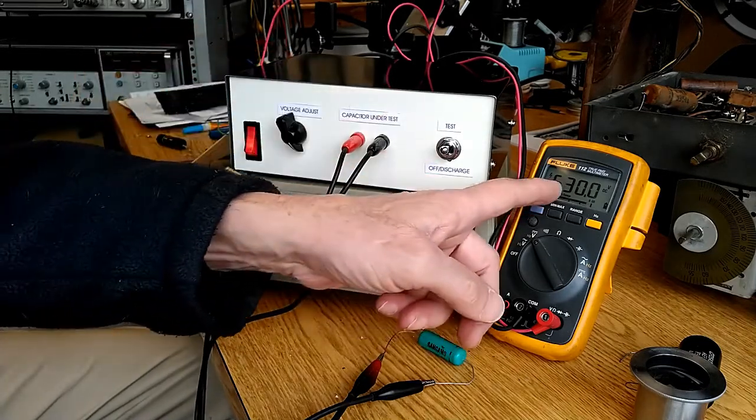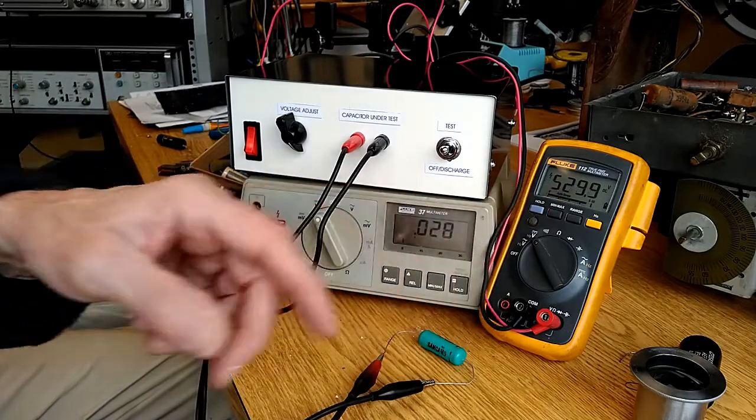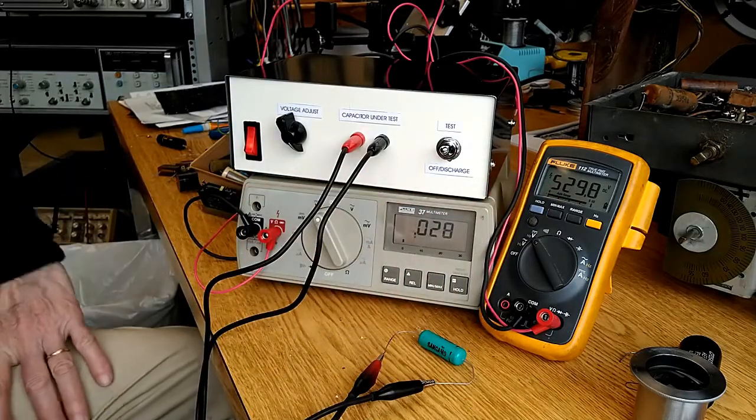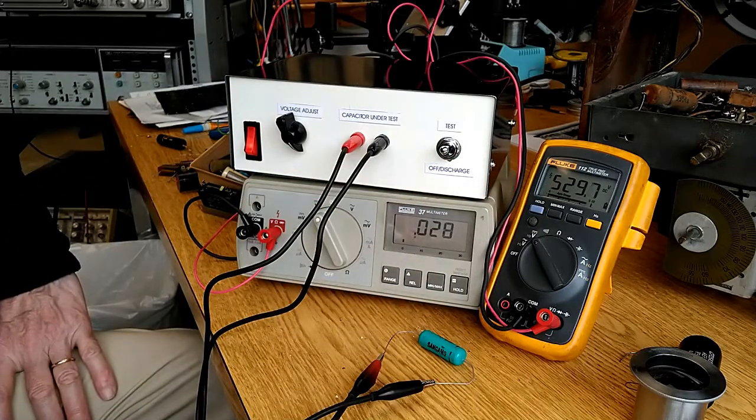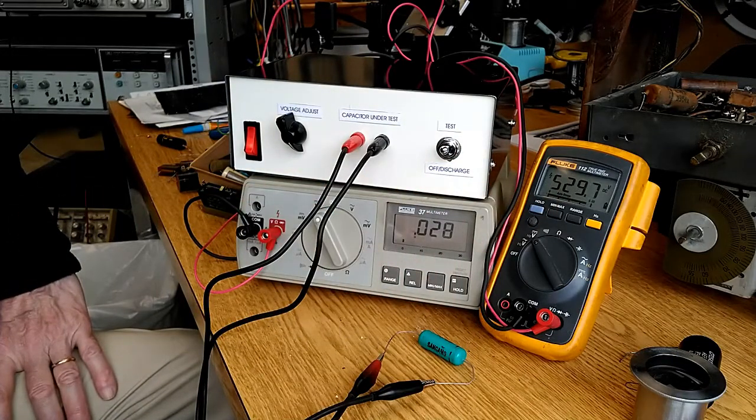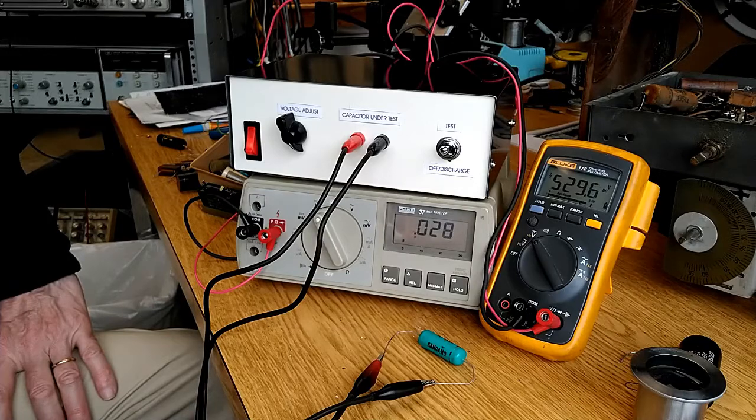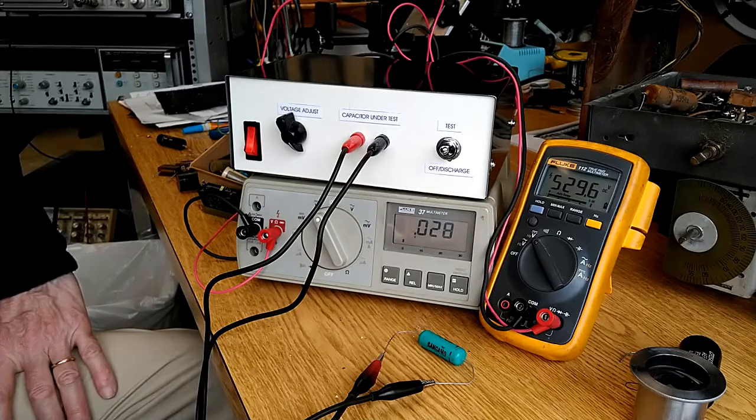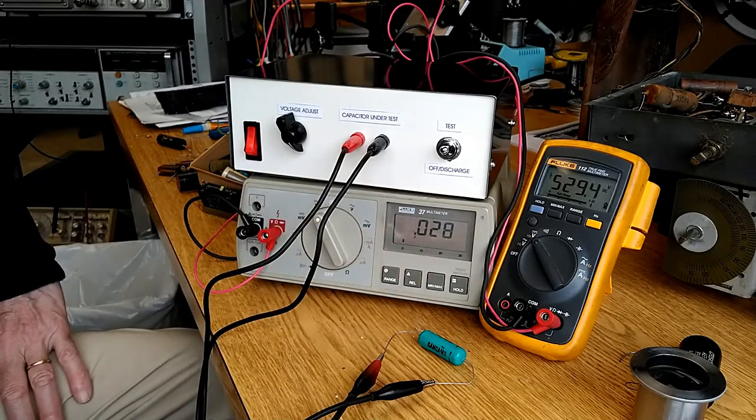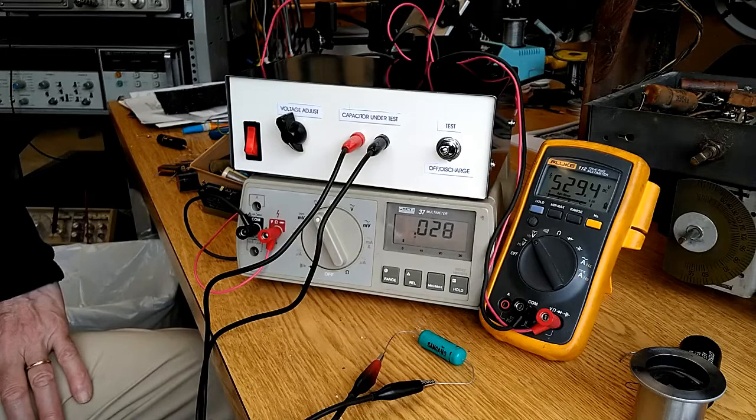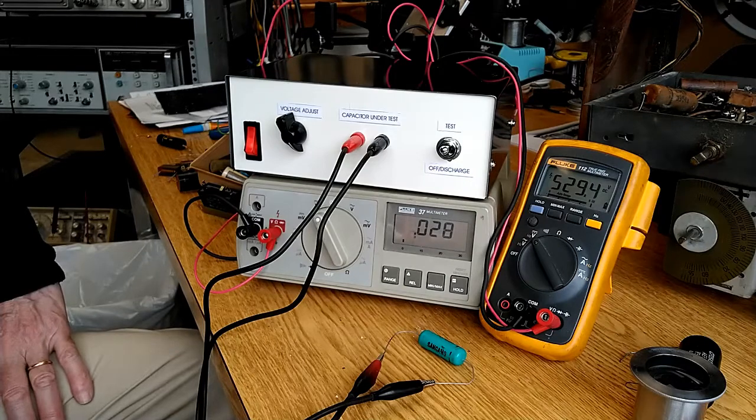We can't get quite up to the 600 volts of the capacitor rating. Looks like the limit on this unit is about 530 volts. But I am seeing about 28 microamps of current through the leakage tester.